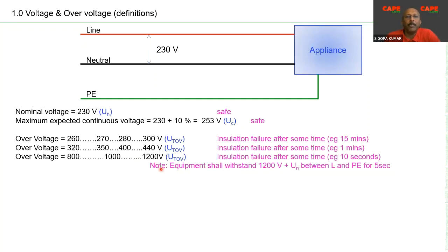Between line and earth, due to a high voltage fault, all equipment connected to a line must be able to withstand 1200V plus nominal voltage — approximately 1430V — between line and PE for five seconds. This is a standard requirement.